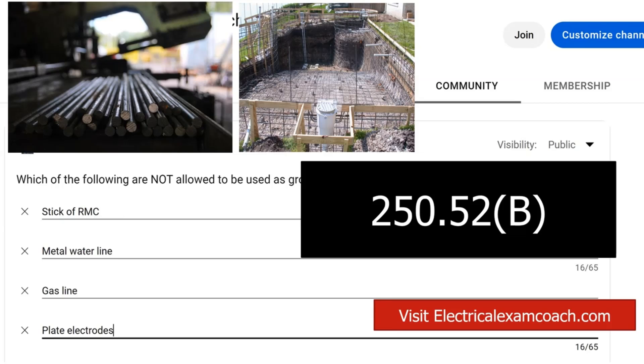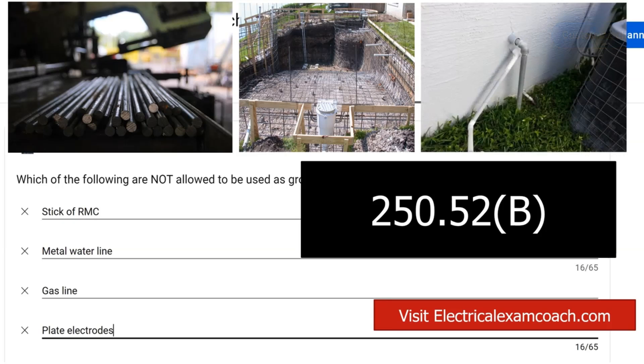The third one — and the answer for our question today — is that you're not allowed to use a gas line as a grounding electrode. This doesn't mean you may not have to bond the gas line, but you're not allowed to use it as a grounding electrode. This one just makes tons of sense: we definitely don't want to be carrying any surges or lightning strikes on the gas line intentionally going down to earth. The answer for today can be found in NEC 250.52(B).